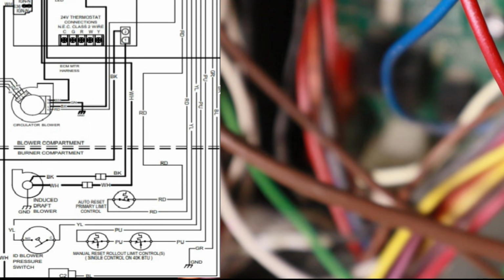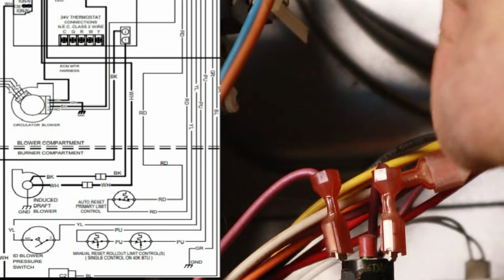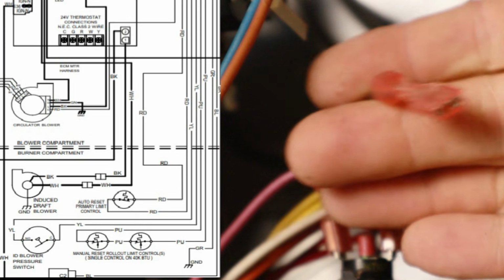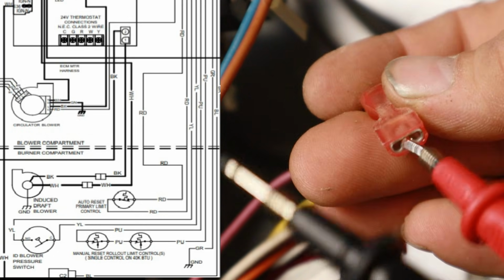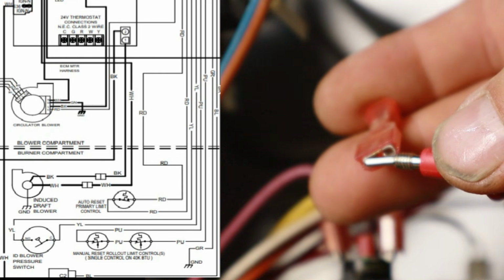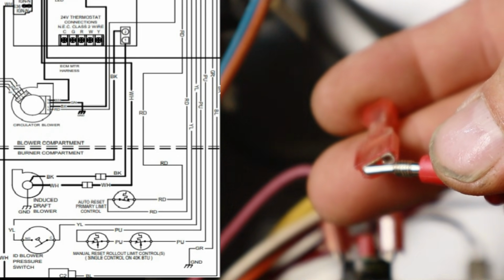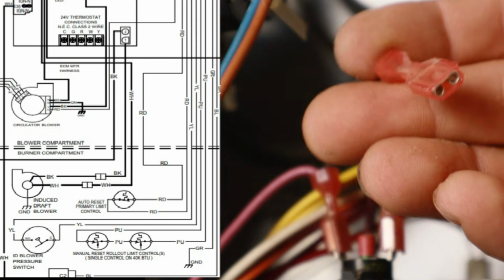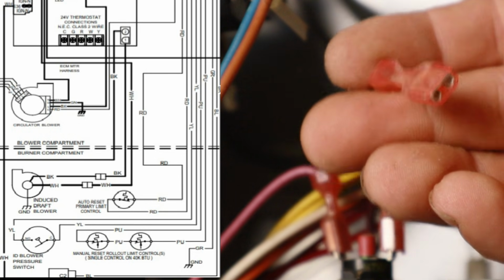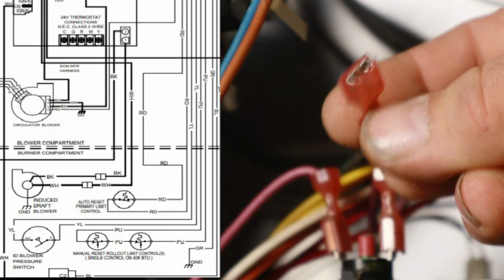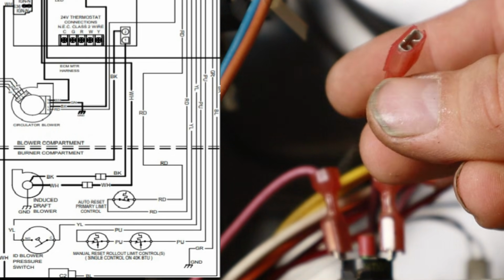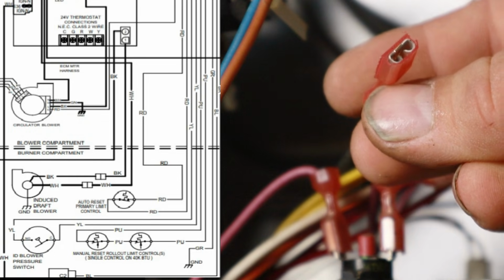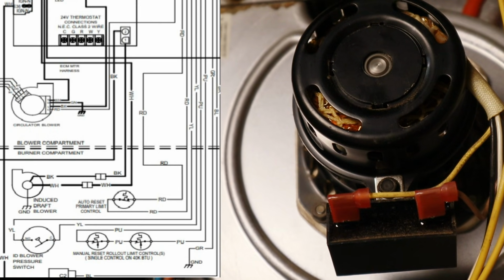Because our inducer motor is not starting right now, this could be a couple of things. We have to test and see whether or not our control board is actually putting out 120 volts on that wire. So when I come back up, and this is the wire coming from that Molex plug on the control board, if I were to go ahead and test for voltage there on ground, I am reading 125 volts. All right, so from here to ground, I'm reading 125. So that's telling me the control board is actually sending the power out, but obviously because it's unplugged, the power's not making it to the inducer motor. So I'm going to go ahead and plug that back in, and our inducer motor should immediately start. And as you can hear, the inducer motor is now running.